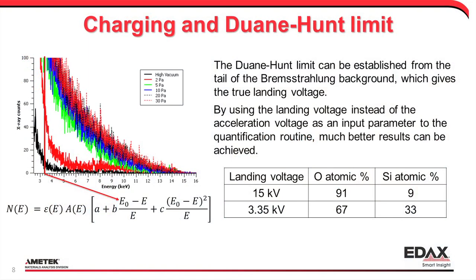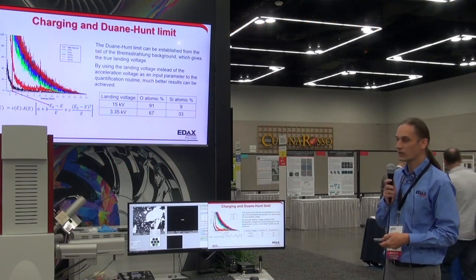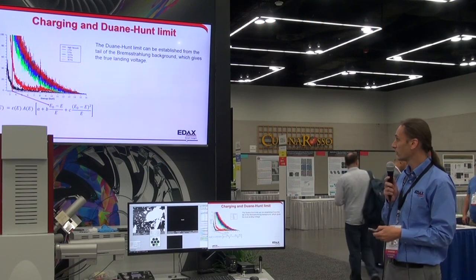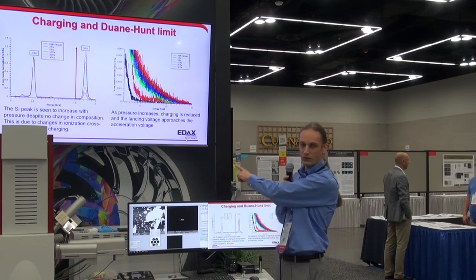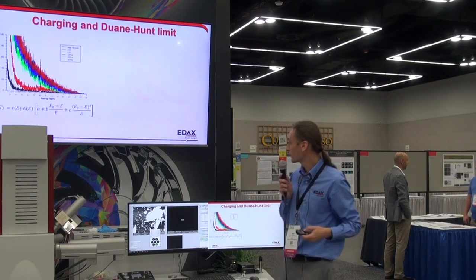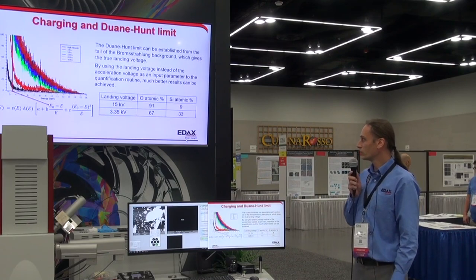We're supposed to have 15 kilovolts coming down — that's my acceleration voltage. But if I click the quant button on this high-vacuum spectrum telling the software we have 15 kilovolts of landing voltage, it's going to be garbage: it will tell me I have 91 atomic percent oxygen and 9 atomic percent silicon, because the oxygen peak is significantly higher than the silicon peak.